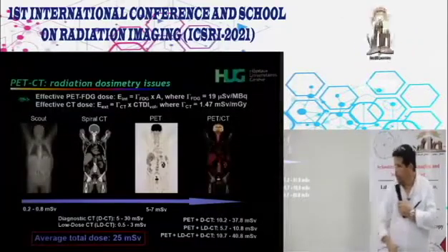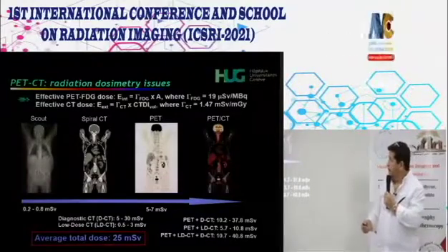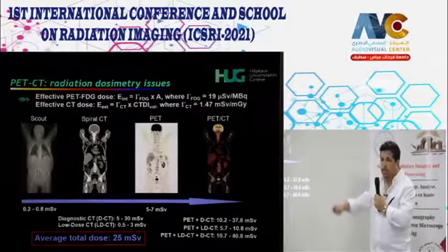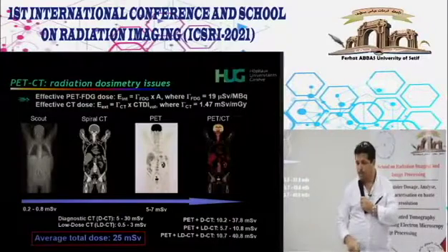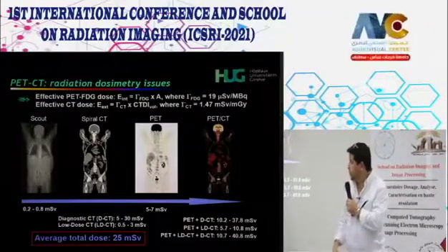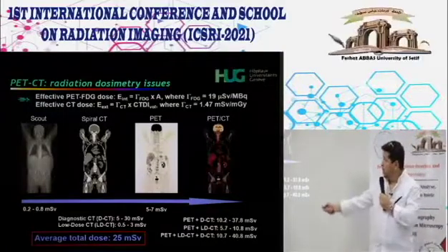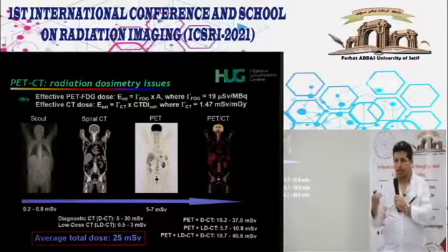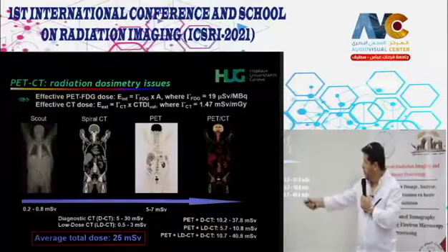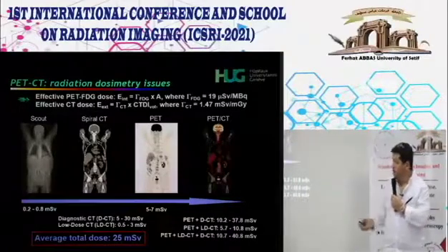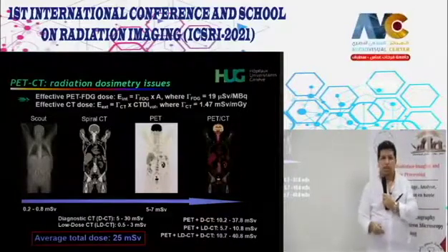And this is exactly your question regarding the radiation dose delivered to patients, which could be an issue. Because you're basically adding up the contributions from the different imaging modalities. SCOUT scans, so this is between 0 point something to 0.6 millisieverts, depending on the acquisition parameters. Spiral CT is usually a low dose scan that we use only for attenuation correction and anatomic localization. Few millisieverts still. The injection of the tracer, so we usually inject between 200 and 300 megabecquerel, so between 5 and 7 millisieverts.